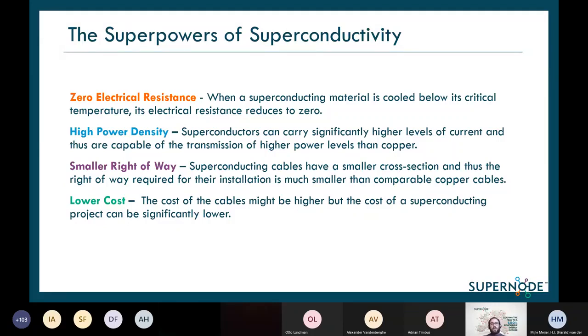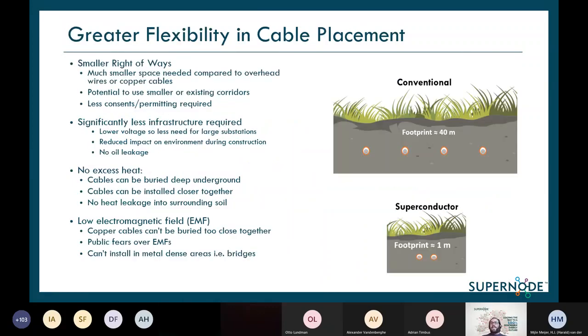Just to touch a bit more on this footprint, the image on the right is an example of the SuedLink project being built in Germany. As currently stated in the project, the spacing between poles will be about 10 meters, requiring two sets of bipoles of 525 kV cables. You can see the difference in footprint between the conventional system as it exists in the project today versus a superconductor, which is capable of carrying the same 4 gigawatt power but using only two cables.